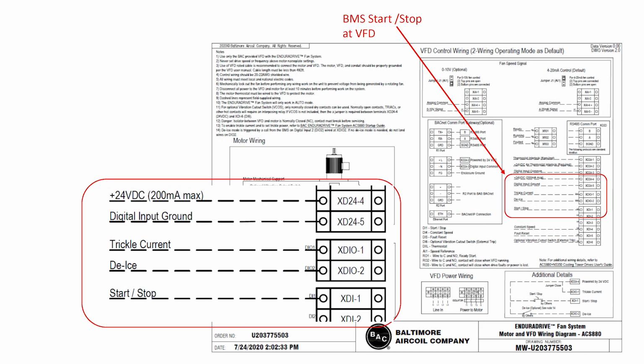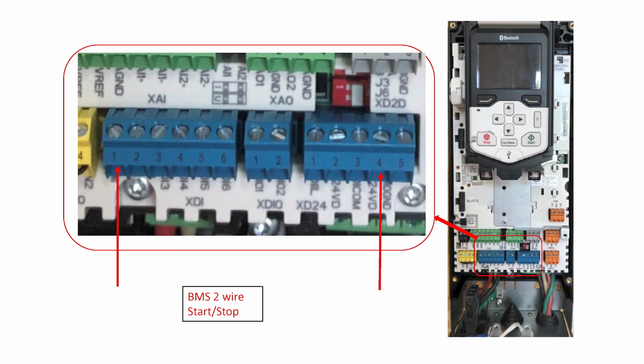After completing the wiring for the BMS speed signal, let's ensure the BMS wiring for the BMS start-stop or run command is complete. You will need to install either a 2-wire or 3-wire start-stop signal. To install the 2-wire BMS start-stop, wire the leads to terminal XD24-4 and XDI-1. Note, close equals start and open equals stop.